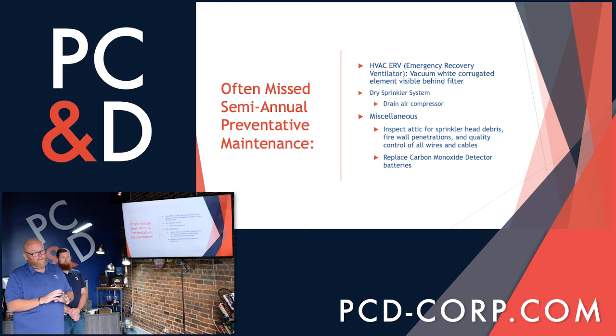Heaven forbid we had a fire in that attic. We want to have all of our sprinkler heads exposed and open, free of debris. That enables them to trip at the appropriate time, and it also enables them to spray their water pattern the appropriate way to cover all of the area that possibly could be affected.